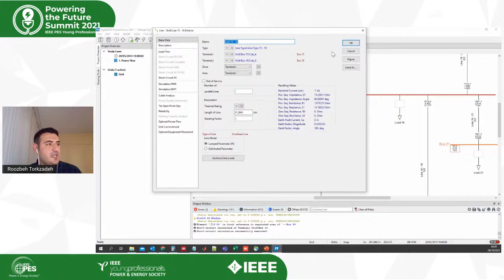But when we move further away from this bus bar, for example, to bus number 15, there is one line between them, and this line has a length of about 38 kilometers. So there is an impedance between these 2 points, and you can see here that the voltage at this bus bar is 0.17 per unit, not 0. So the further we get from the location of the fault, we can see higher values for the voltage dips.